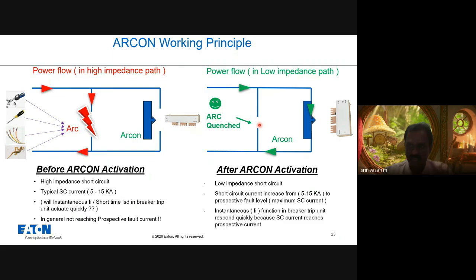Once the low impedance short circuit is created and the prospective fault level is reached, the ACB or any other breaker will be signaled to trip. So the power feeding to the switchboard will be totally isolated. But the point to be noted is that by having the Arcon, you can put the switchboard back into service by doing a simple cleaning operation. There is no need for any major replacement.